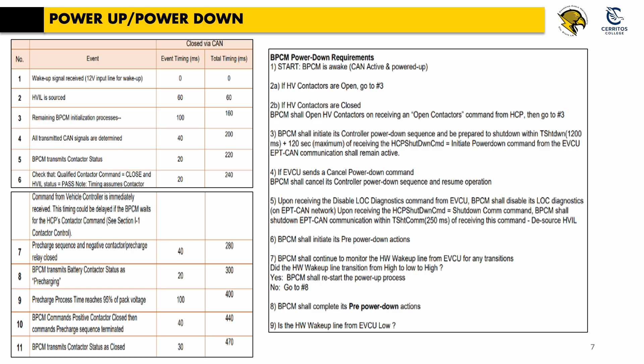First, the presence of a valid high-voltage interlock, or HVIL, loop is confirmed. If we don't have a valid HVIL signal, then we immediately flag the fault and halt the sequence. If HVIL passes, the BPCM checks for other faults and closes the pre-charge contactor if none are found. If faults are found, then they're immediately reported and the process stops.